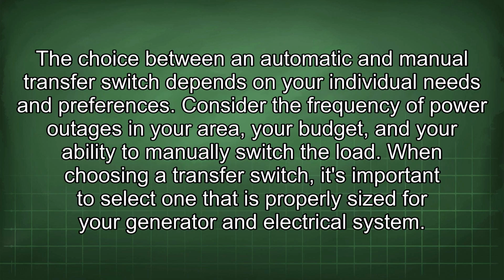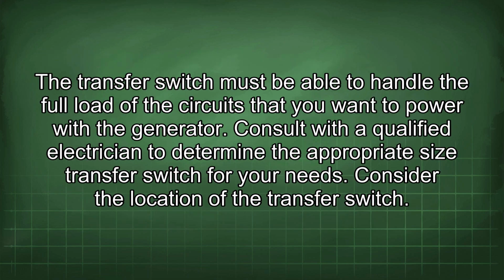The choice between an automatic and manual transfer switch depends on your individual needs and preferences. Consider the frequency of power outages in your area, your budget, and your ability to manually switch the load. When choosing a transfer switch, it's important to select one that is properly sized for your generator and electrical system. The transfer switch must be able to handle the full load of the circuits that you want to power with the generator. Consult with a qualified electrician to determine the appropriate size transfer switch for your needs.